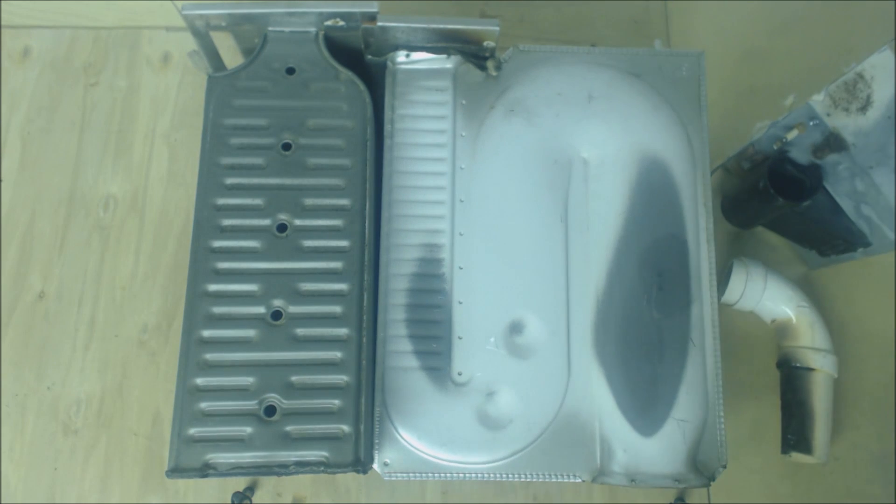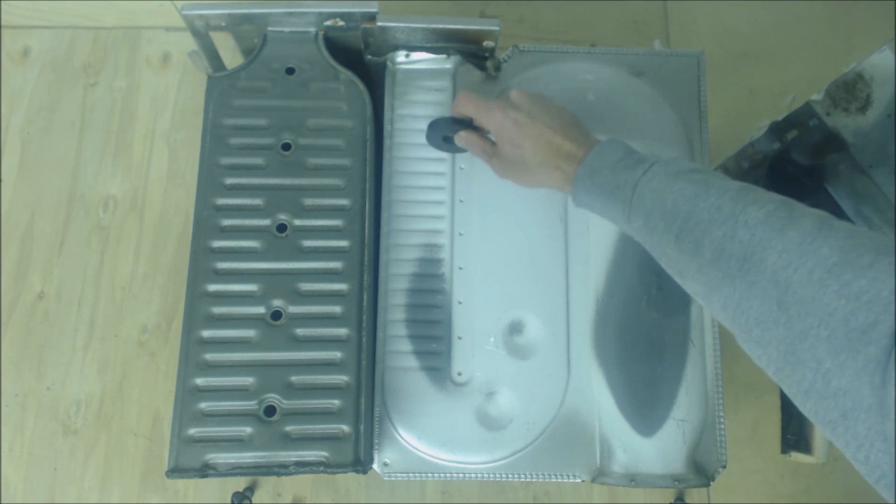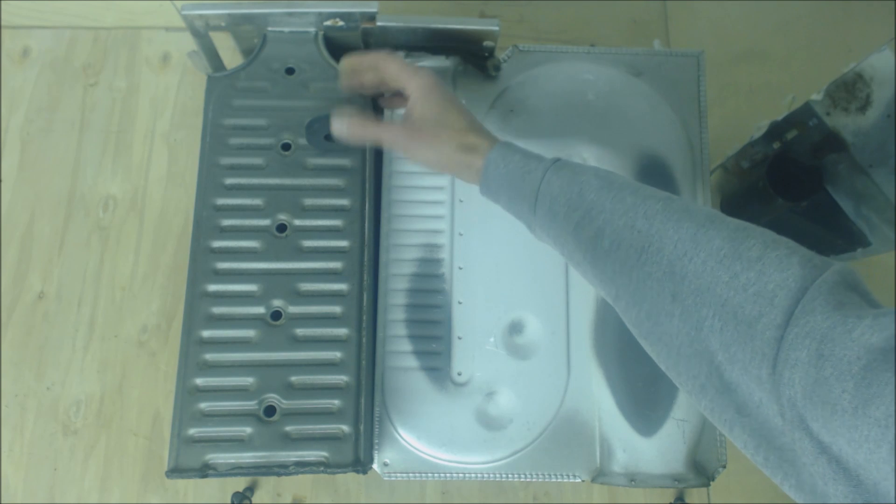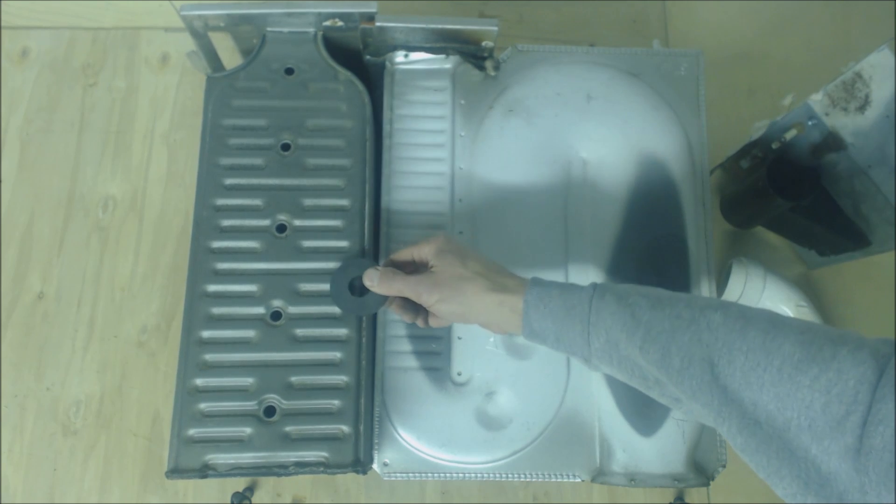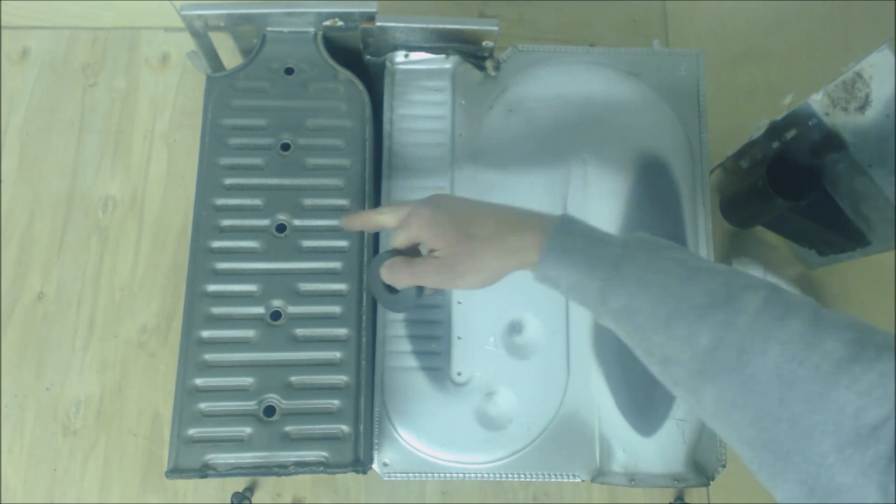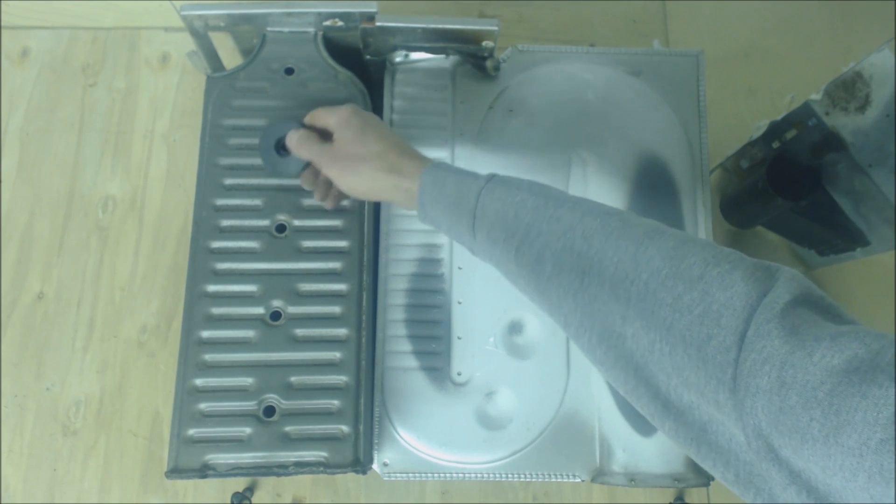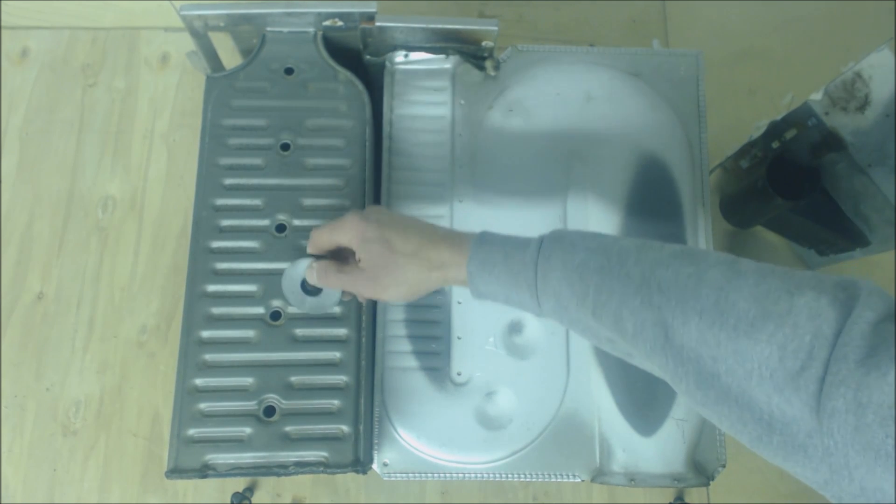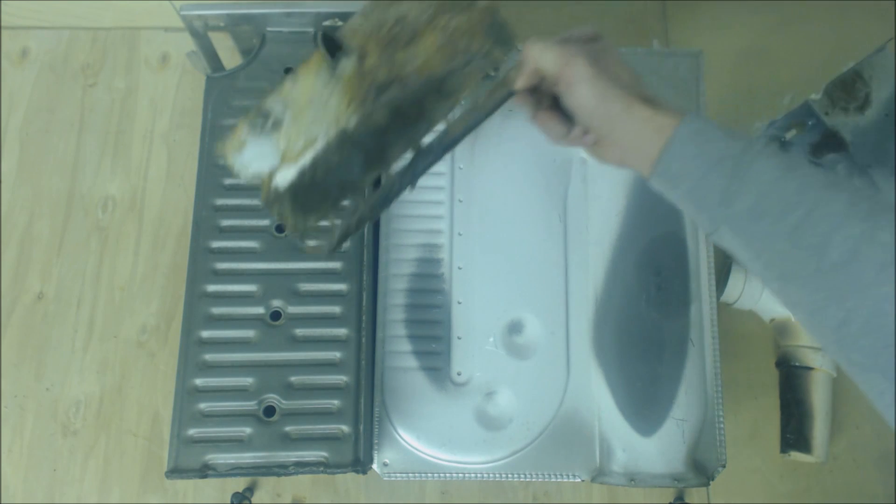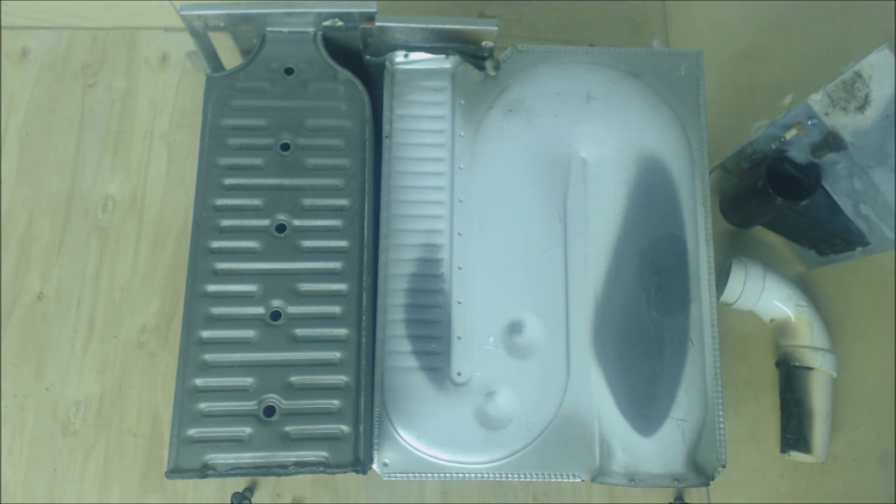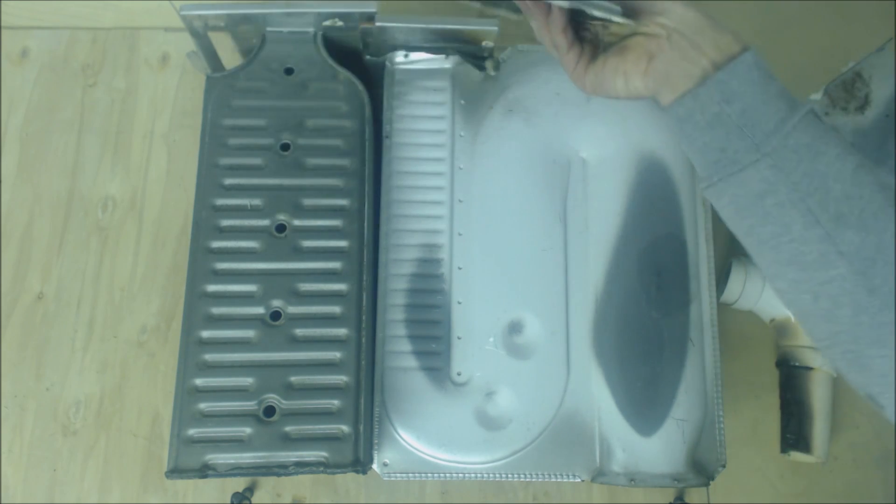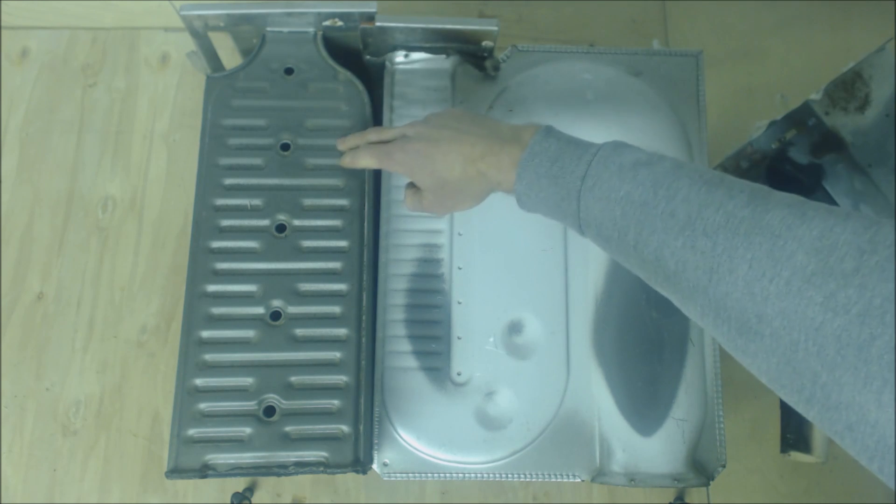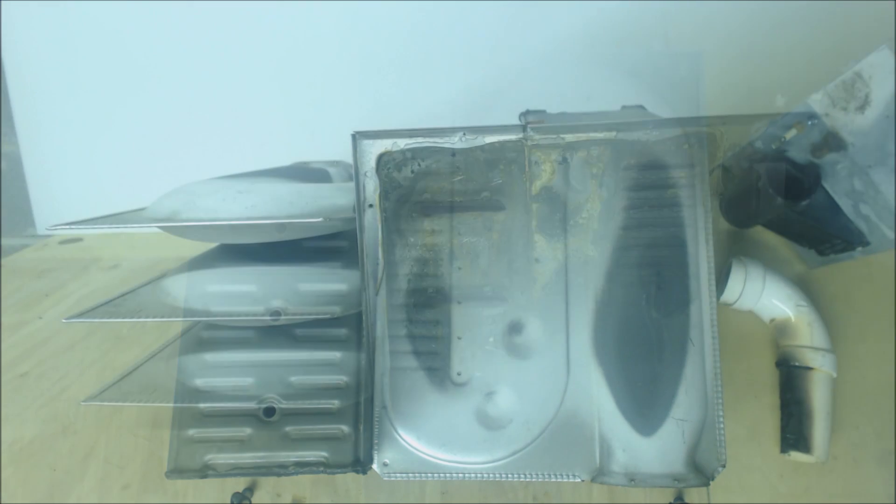Here's an issue. The normal heat exchangers are made out of steel, galvanized tin. Look here - you have water condensating here, and it's the same material. It's not exactly the same material as this, but it's still a metal that's going to rust regardless of what surface protection was put on it. That's a problem. This is along the back side right here. That plate was pulled off as well. Here is the other plate that holds all the exhaust to connect the primary to the secondary.